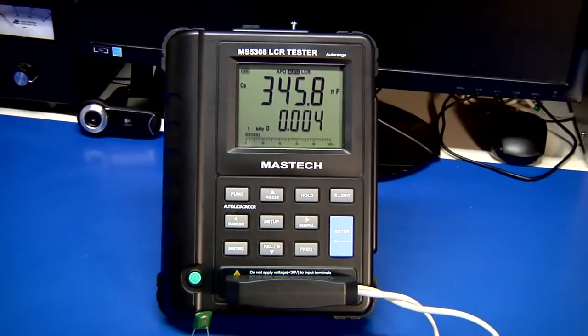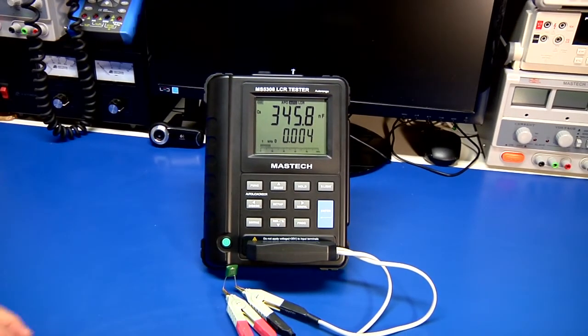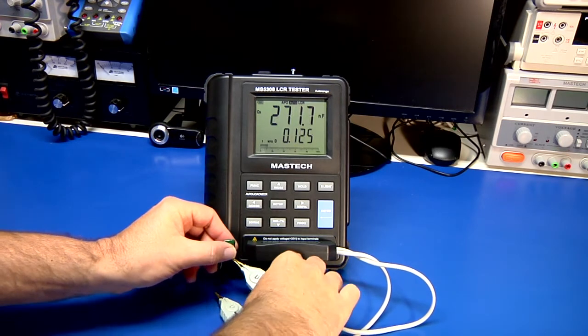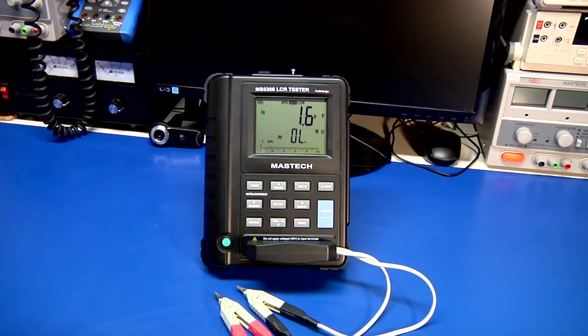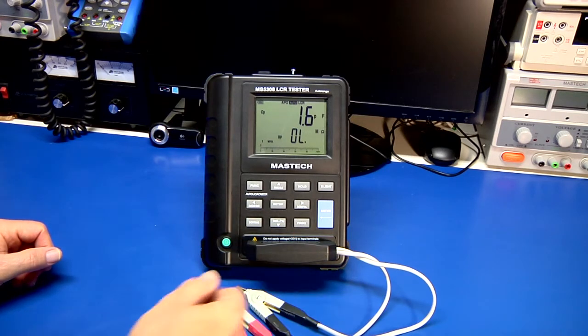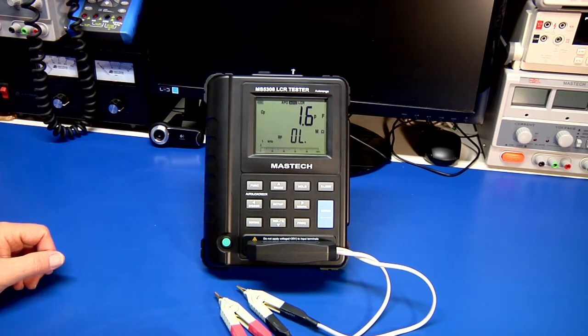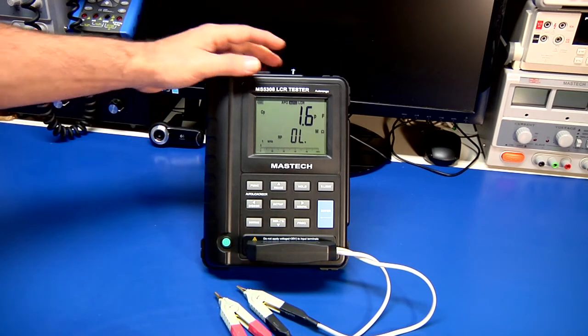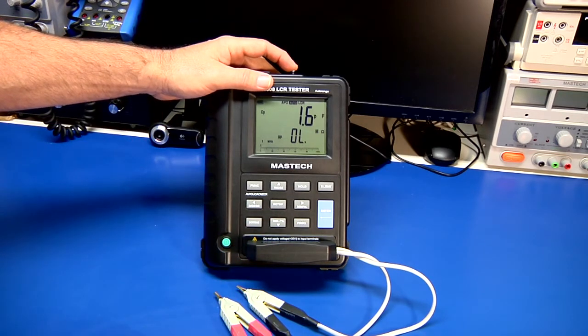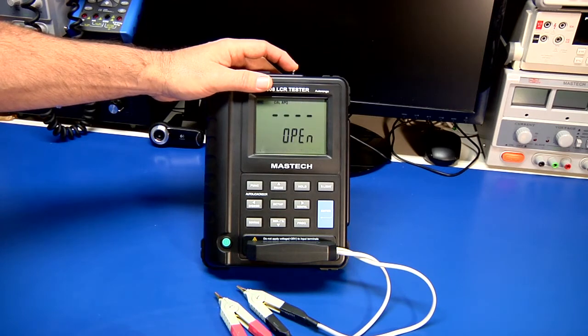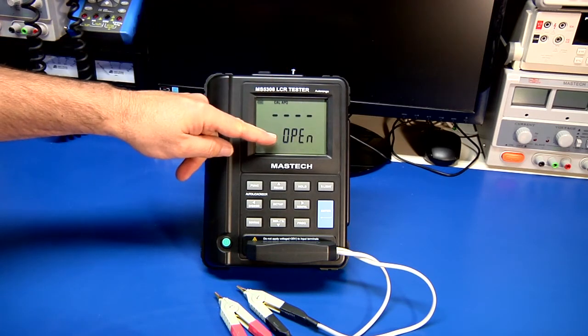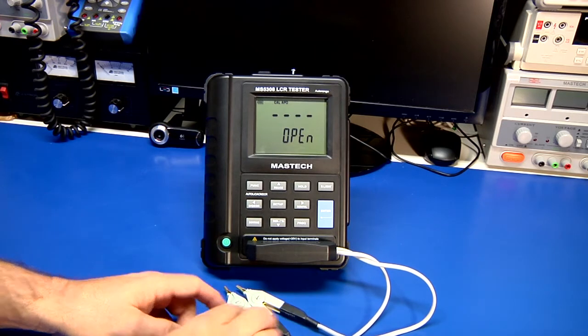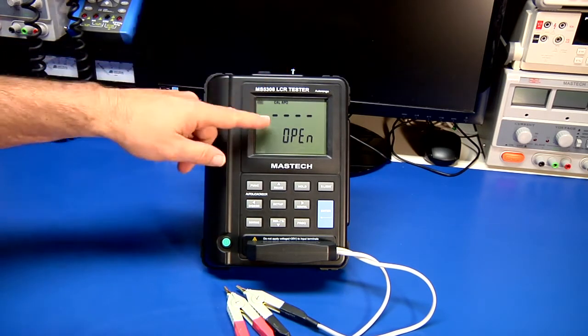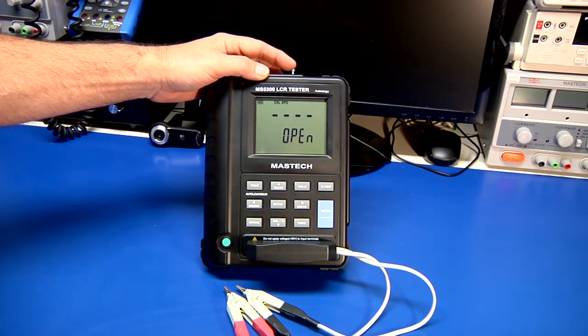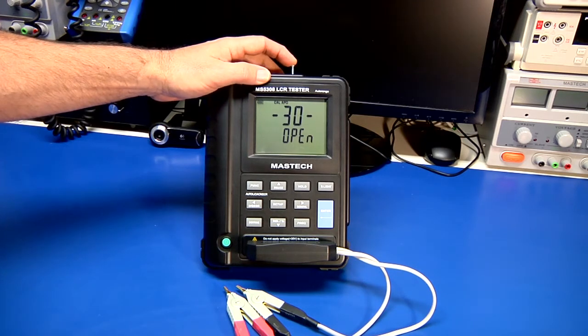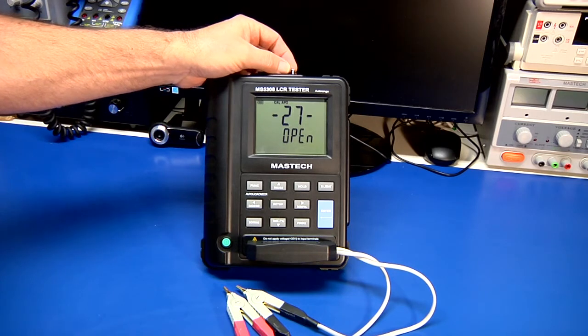So if we back out to here where you can also see the clip leads, what you do is you disconnect and set up the jig you want. This whole process is to get rid of the parasitics and stray capacitance, inductance, and resistances. So you're sort of calibrating the meter to the test leads and fixtures. What you do is press this to enter that mode, and you'll get an open indicator, and open means have the test leads open so they're not connected together. Then you press it a second time and it'll do a 30-second countdown as it does its calibration. So I'm just going to press this again. You can see we have the 30 right up there, and it's counting down.